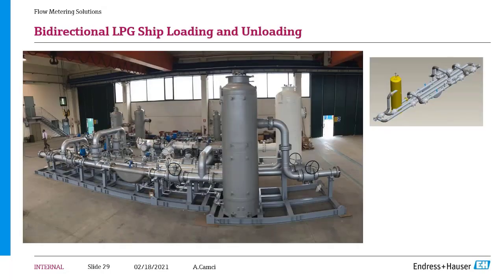Then I will jump to another LPG loading, but this time it is also an unloading system, which is bidirectional. When you have an air eliminator installed on the system, the skid direction is always the same, because air eliminators have one inlet and one outlet fixed. Therefore, to use it in both directions, we designed a system with the pipes you see in the middle, with which we can always keep the liquid passing through the skid in the same direction.